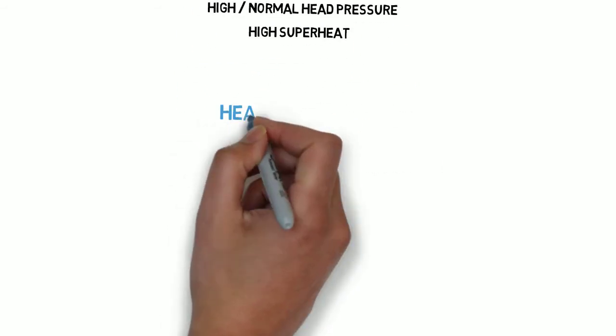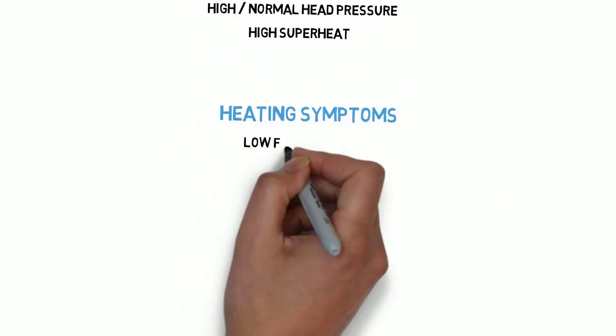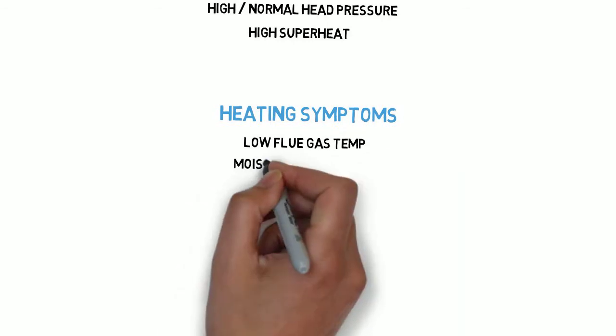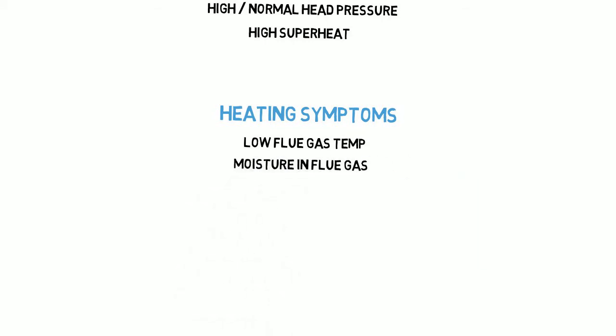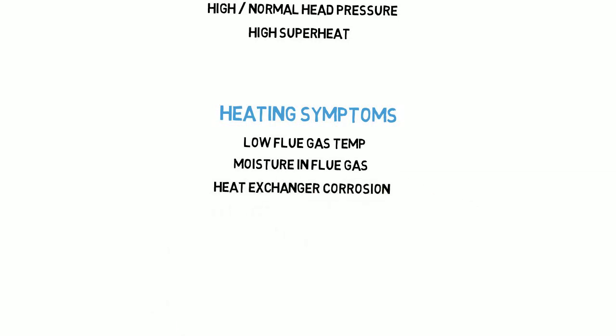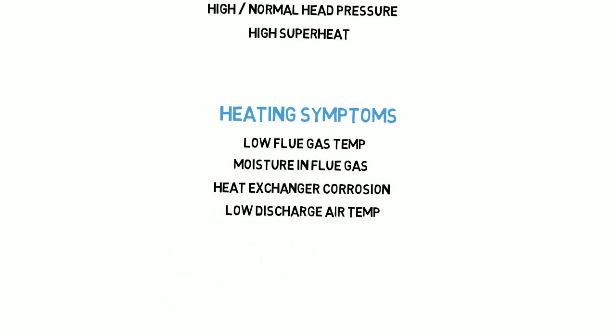Heating symptoms of high air flow: low flue gas temperature, moisture in the flue gas, heat exchanger corrosion, and low discharge air temperature.